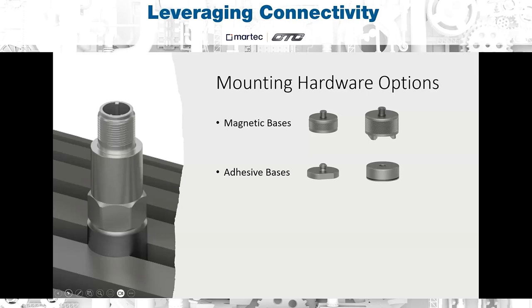The next option is adhesive bases. These bases are used for permanent mounting applications. This is typically when drilling and tapping the machine is not a possibility, or if there's no flat area. We can also offer motor fin mounts that you can see in the picture to the left of this slide. These mounts are epoxied between the fins of the motor. Finally, we have the Zerk adapters. So that was just covered in the lubrication slide, but again, these can be used with a grease gun to apply grease to the bearing while taking your vibration reading.